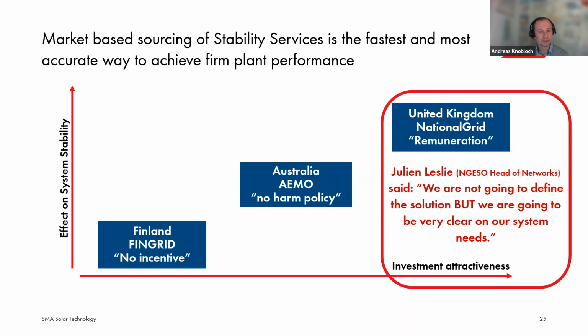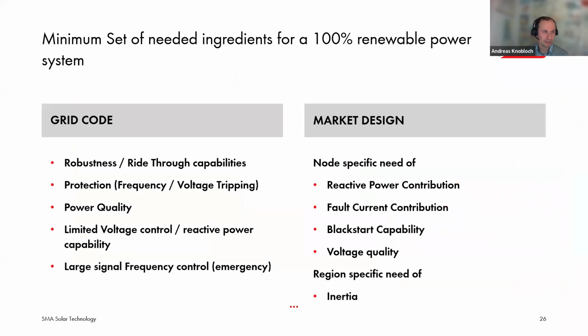And in the United Kingdom, we see a different approach, and this is remuneration. So they initially try to introduce stability service markets that are demand-oriented. And if you look at the effectiveness on system stability, if you have mandatory requirements where all should provide something without any incentives, then the industry will try to give as little as possible. And if it gives as little as possible, the effect on system stability, of course, is not that much. The highest effect we would achieve is if it is remunerated, and if it's remunerated, you can also demand what you would like to have, the quality of power supply and response. It is the best way and the most effective, also in our opinion, for how systems should be realized.